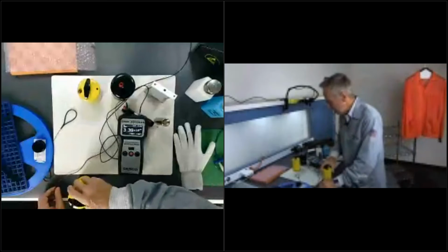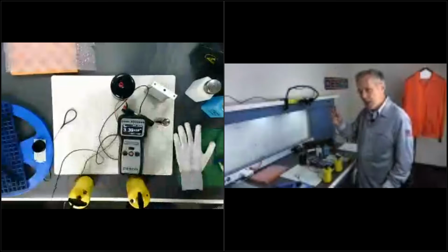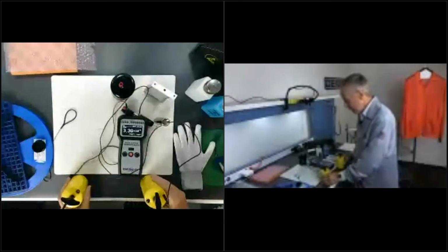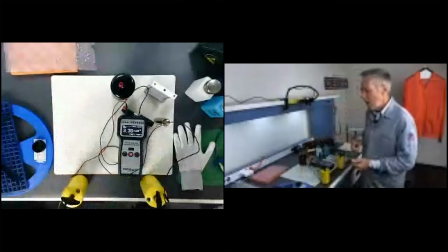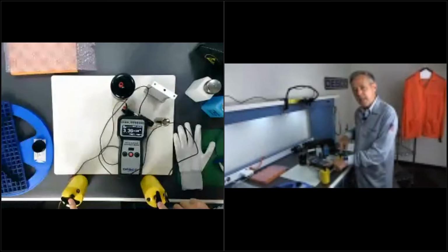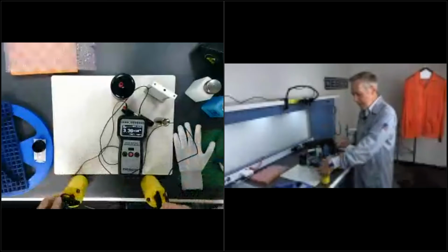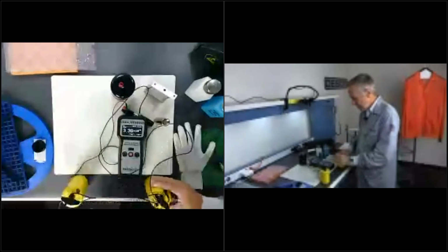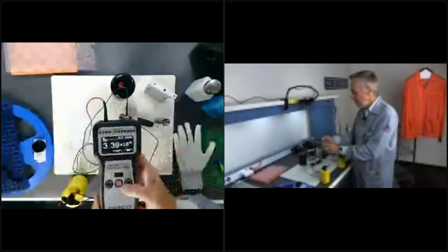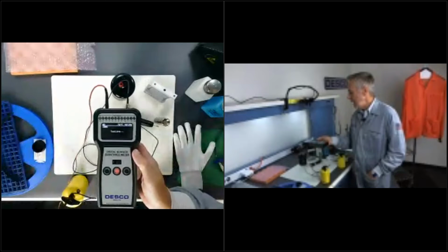So the first thing I would want to do is make sure the surface resistance of the mat is good. So I'm going to come back here. I'm going to take my other 5-pound probe. Now, when I'm checking RTT of work surfaces, the requirement is that I set my probes 10 inches apart. So we make this cool little adapter here that's set at 10 inches, and I can simply clip on my probes here and I get my exact 10 inches. So that might make life convenient for you. Again, I'm going to take my measurement, and I have to wait the required time.